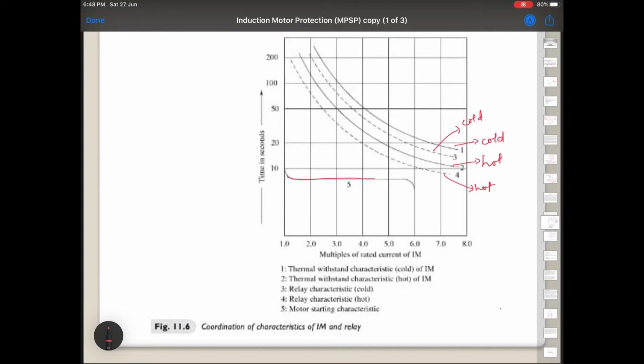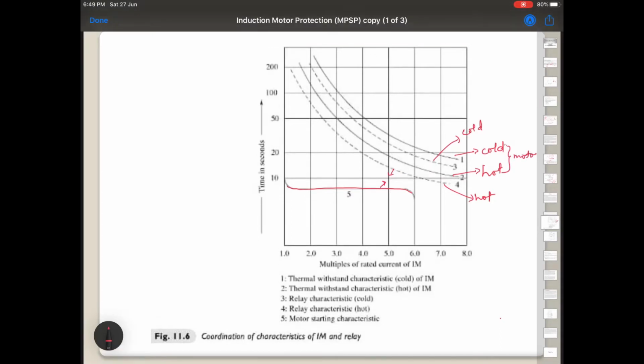So this is the starting characteristic of the motor, and you should never have this curve and this curve overlapping. Why, we'll see in a coming slide. This is for the motor, and this is for the thermal relay. Curves 3 and 4 are drawn in terms of CT primary currents as the relay is fed through the CT. The ordinates of curves 3 and 4 give the time of operation of the thermal relay for a given CT primary current, and that primary current is in multiples of the rated current of the motor.